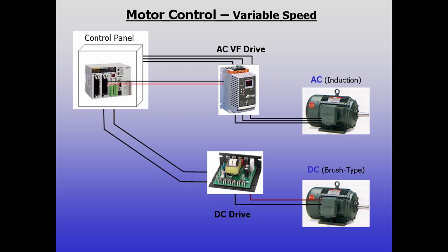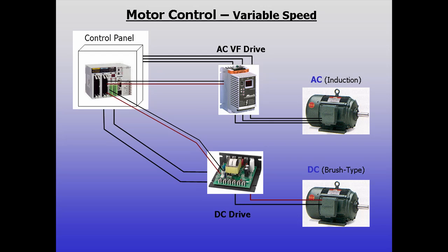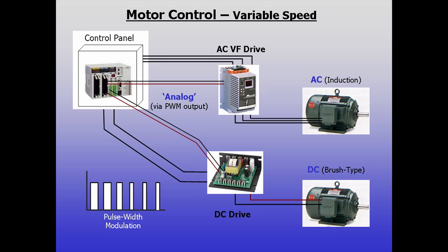If a higher level of control is needed, usually for varying speed, controllers can actively command drives with variable signals. Most AC or DC drives can follow either analog voltage or current. Industry standards are 0-10 volts DC or 4-20 milliamps. Solid state controllers can synthesize analog using varying PWM waveforms, but this technique is limited to drives rated to accept it.